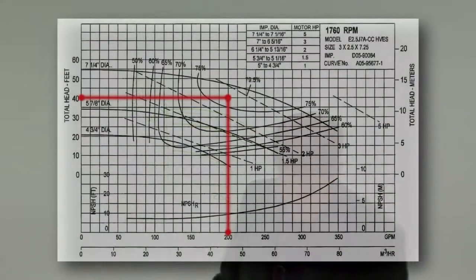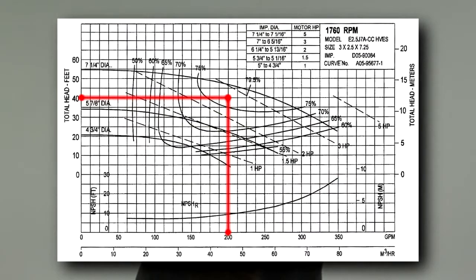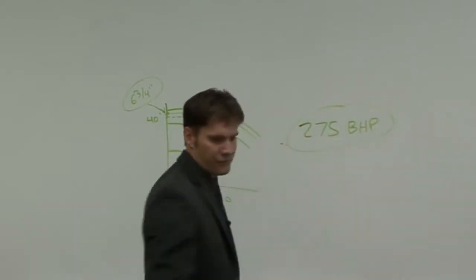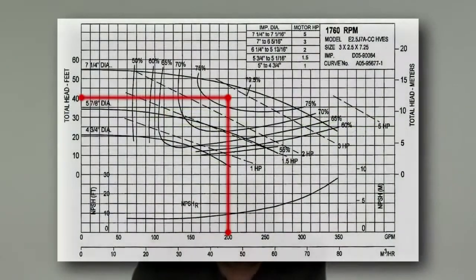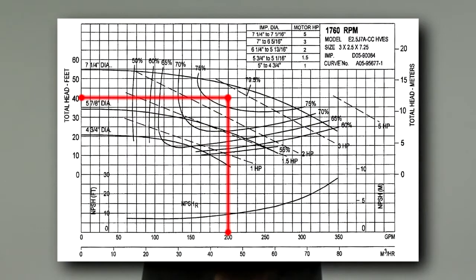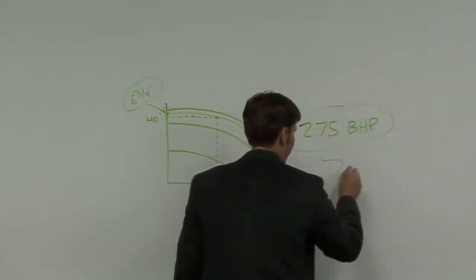My brake horsepower on this curve, well, we're in between 2 horsepower and 3 horsepower, but we're a little closer to 3 horsepower. So we could estimate maybe 2.75 brake horsepower at that point of operation. We could look at our efficiency curves. Our efficiency, we're in between 75 and 79.5, so we could say we're probably close to 77. We're 77% efficient.